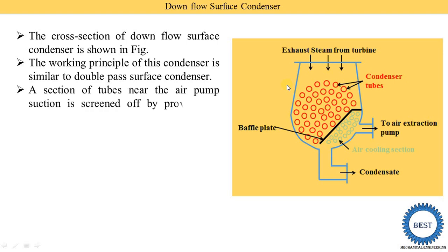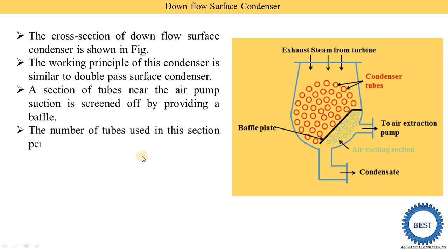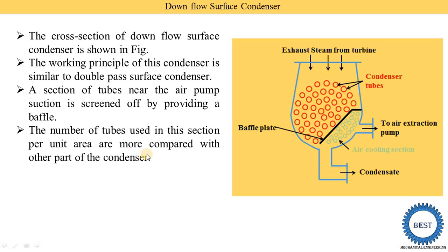A section of tubes near the air pump suction is separated by providing baffle plates. The air pump is installed here, and this section near the air pump corresponds to the green colored tubes. The number of tubes used in this air cooling section is more than in other parts of the condenser — suppose in a one meter square area of the main section there are eight tubes, while in this region there are 12 or 15 tubes.